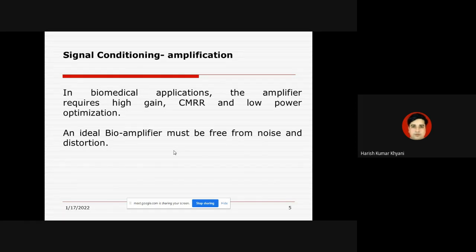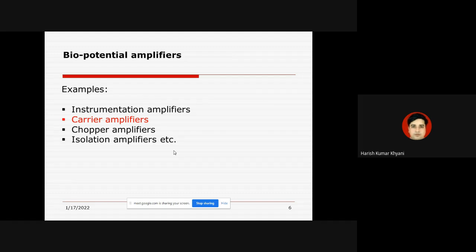In biomedical applications, normal amplifiers do not work because the amplifier should have high gain, high common mode rejection ratio, and low power consumption. Most importantly, the biomedical amplifier must be free from noise and any kind of distortion, since it is a very critical field. This slide shows important examples of bio-potential amplifiers, including instrumentation amplifiers mainly used in ECGs and EEGs.